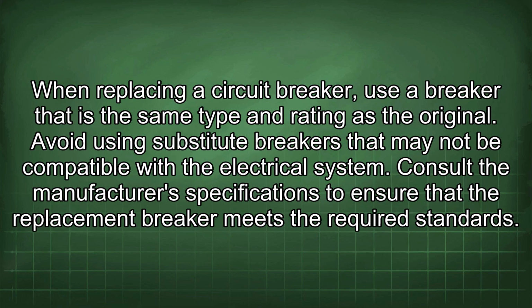When replacing a circuit breaker, use a breaker that is the same type and rating as the original. Avoid using substitute breakers that may not be compatible with the electrical system. Consult the manufacturer's specifications to ensure that the replacement breaker meets the required standards.